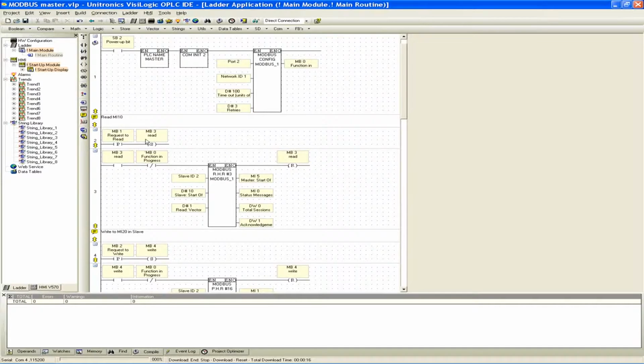So we push the button, we set the read command, and we keep on reading until we have a read that's been finalized and the function block has actually been executed. That is when we reset the MB3 enabler. Again, this 2-net structure is something you can follow in any of your programs, just to make sure that your communication blocks actually do execute. To ensure that your data is being read or written and a successful transmission does occur, you can have this set and hold structure.